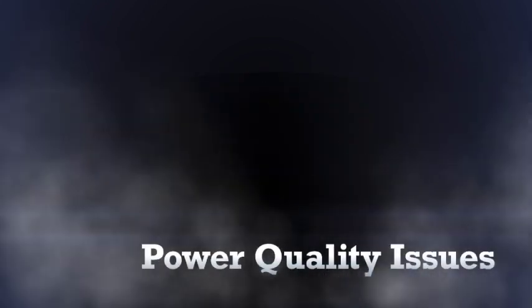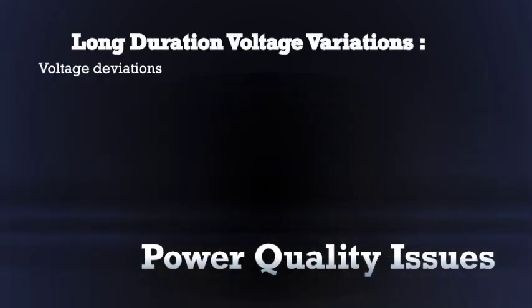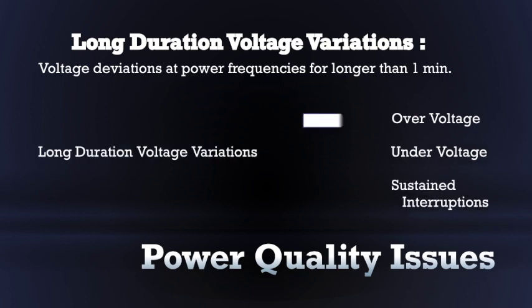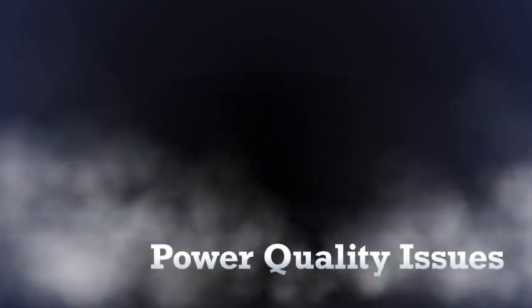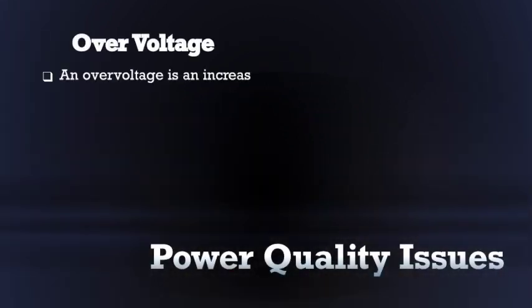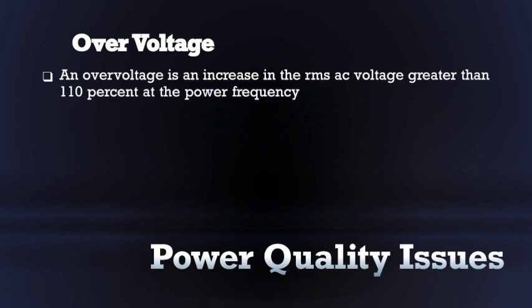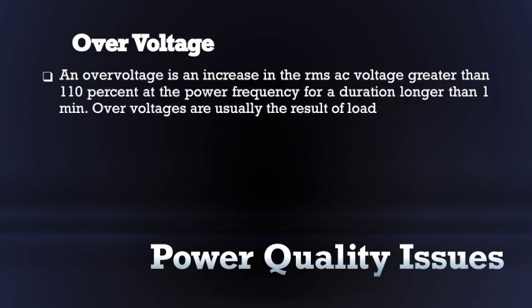The third category of power quality issue is long duration voltage variations. It includes overvoltage, undervoltage, and sustained interruptions. Voltage deviations at power frequencies for longer than 1 minute is what is meant by long duration voltage variations. First we will see overvoltage. An overvoltage is an increase in the RMS AC voltage greater than 110% at the power frequency for a duration longer than 1 minute.